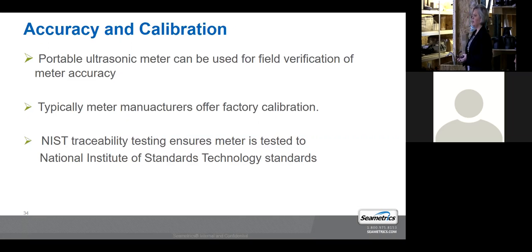So meters can be sent in. There's some third-party people that'll do calibration. Typically, a manufacturer will do a calibration. How often that's done, usually every manufacturer has their own recommendations in their manuals of how often you should do it. Sometimes that recommendation comes down at the district level where they'll say, we want to see that your meter is calibrated annually. I think a good thing to make sure of is that the calibration is always NIST traceable. What that means is National Institute of Standards and Technology. That means that whoever's calibrating your meter, their equipment has been tested and certified to a certain standard. So you know when you get your meter back, it's as accurate as they say it is. NIST traceable is what they call it, if you're sending it out somewhere to be calibrated.